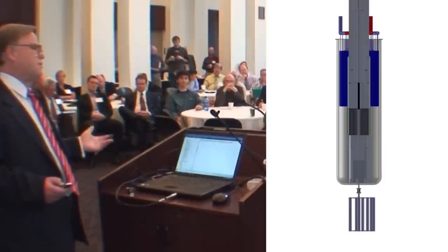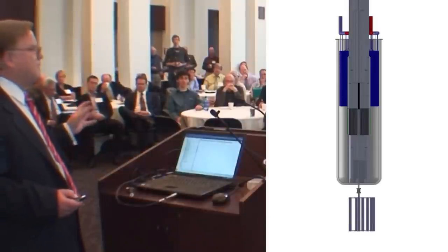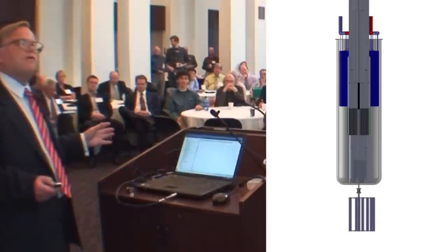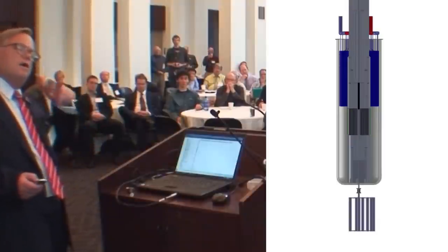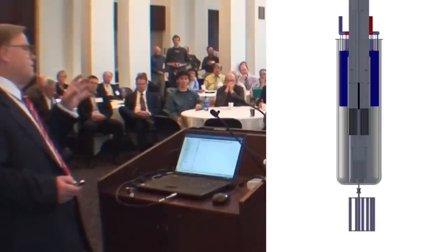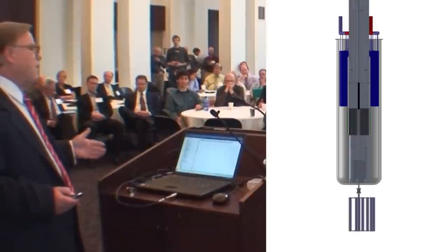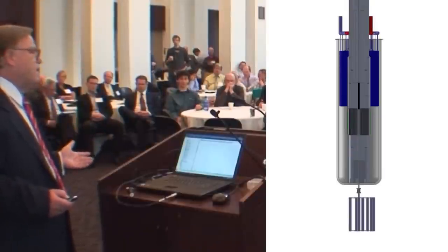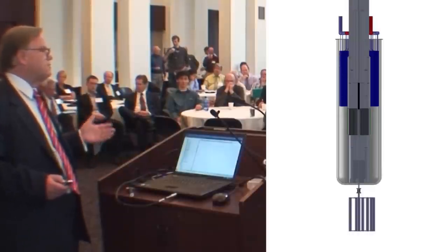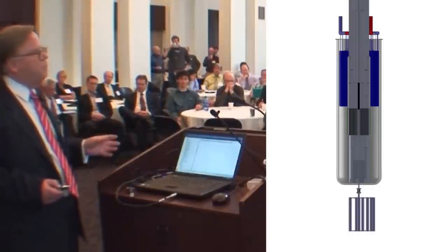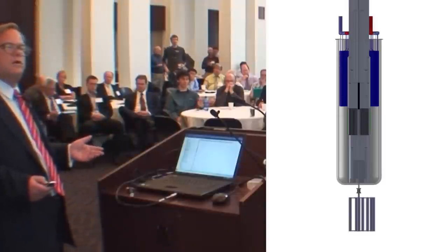That's a large cylinder. And when it's depressed by gravity, let's say there's an incident, so we turn off the electricity, gravity settles this machine out. The first thing that happens is the safety rod goes in and deprives the core of a critical volume. So automatically, in a failure situation, we've already addressed the chain reaction. We've turned it off by moving enough fluid out of the system so that the core is no longer critical.